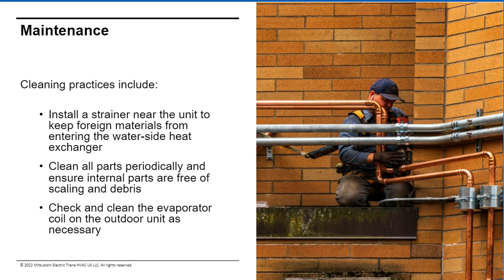Equipment maintenance is minimal for heat pump water heaters. There's a strainer on the water intake side of the heat pump water heater, which should be installed in a manner that makes it serviceable. The condenser coil should be cleaned annually or as needed. You're going to want to back flush the secondary heat exchanger that separates the primary side from the secondary side. The heat exchanger should be installed with connections for flush in place type of maintenance. The maintenance interval is going to vary with water quality, and so that's going to be drastically different from region to region.